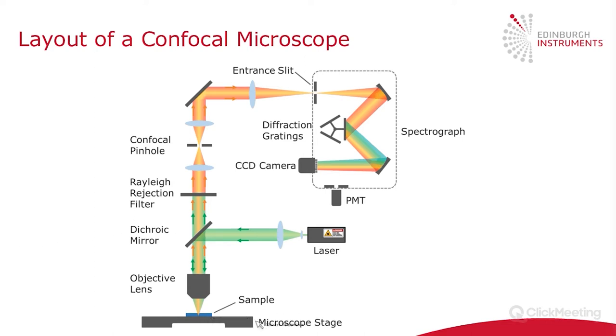The microscope stage can be moved in the X, Y, and Z direction, where Z is the vertical axis. The excitation either creates photoluminescence or Raman, depending on what you want to look at, which is then reflected from the sample and collected by the objective lens in a reflection, or epi, configuration. This photoluminescence or Raman then passes up through the dichroic mirror and through a rejection filter, which blocks the laser wavelength. The signal is then focused down through a pinhole, which is the defining feature of a confocal microscope.